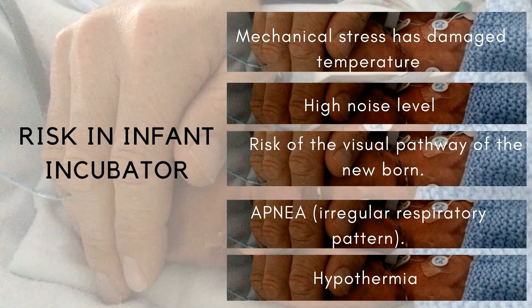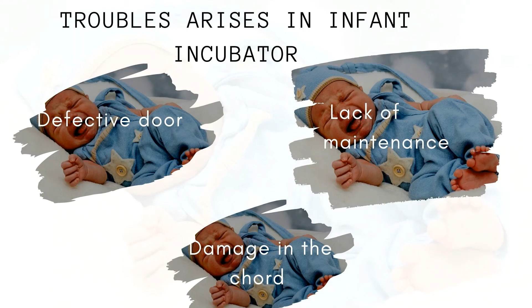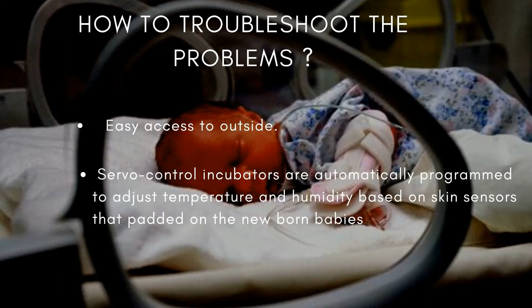Troubles arise in infant incubator. First, a defective door may sometimes cause damage. Lack of maintenance results in the use of incubators with high ambient noise levels, caused by a misaligned air circulating fan, resulting in hearing loss. Sometimes damage in a cord also causes problems. This is about troubles that arise in infant incubator. Next is how to troubleshoot these problems. Servo control incubators are automatically programmed to adjust temperature and humidity based on skin sensors that are padded on the newborn baby. Open box system provides radiant heat from above the baby, with easy access from outside.